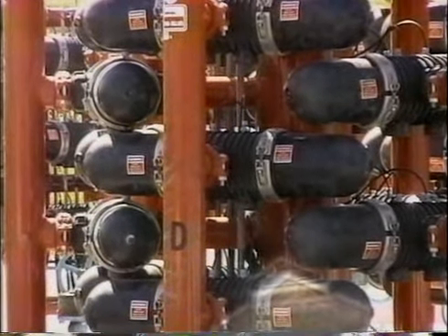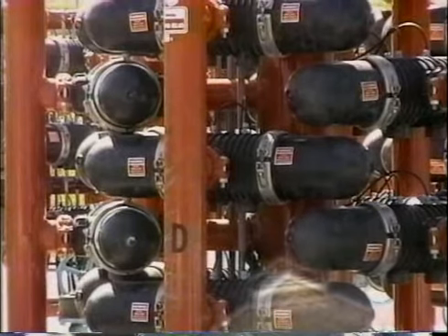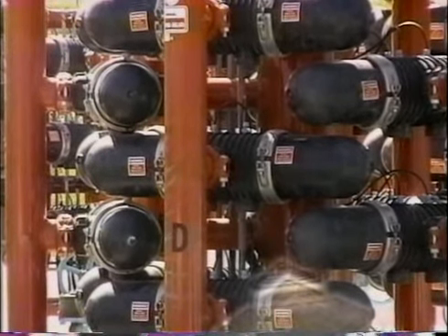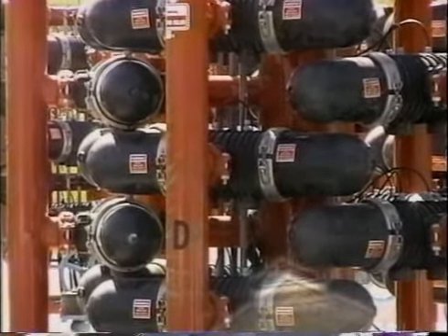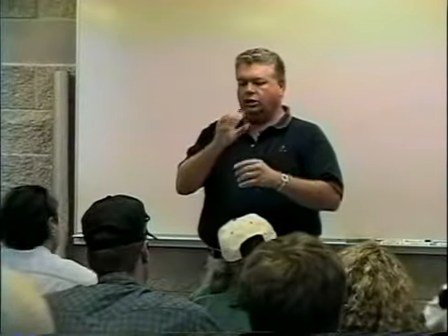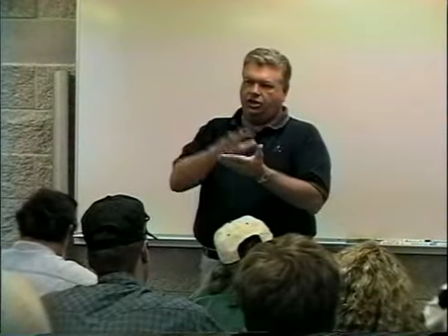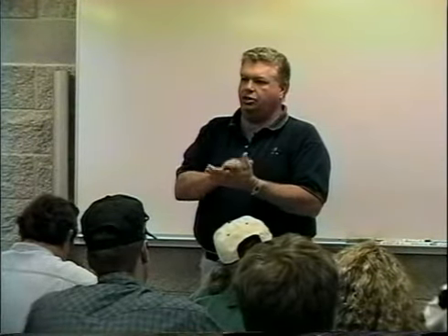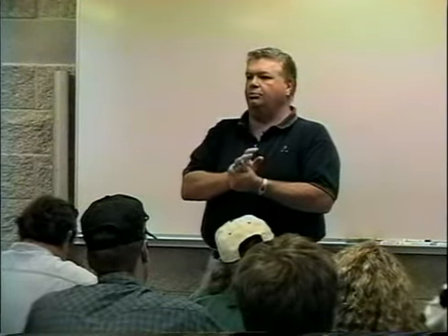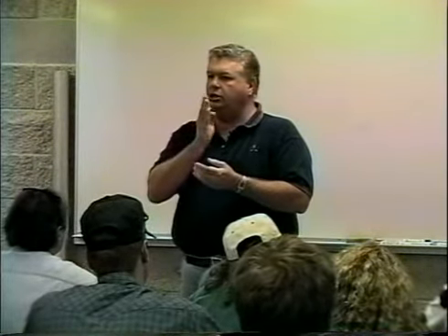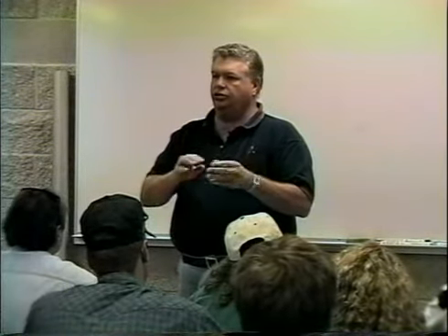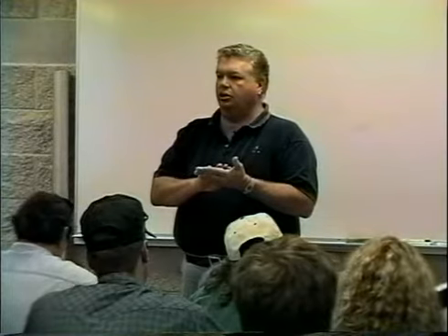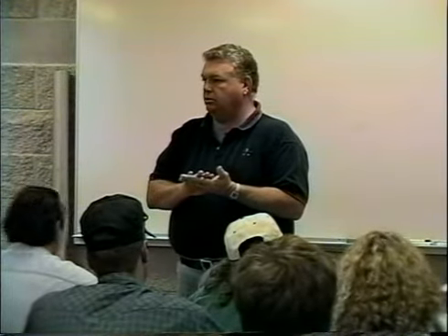One of them is a disc filter. You just have stacks of discs on top of each other with very small gaps between them, and they're generally about yay big around, and water comes up through the center and has to work its way through these discs, and they're just compressed down on each other. They look almost like an LP record, except instead of slotted around, they have little tiny slots radially in them. And as the water tries to get through it, the debris gets caught in the little slots.